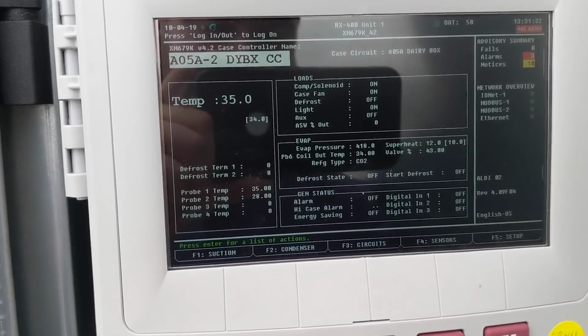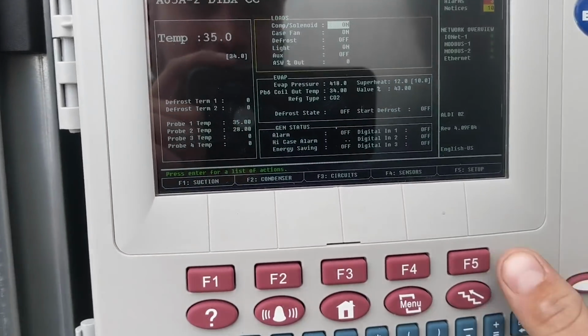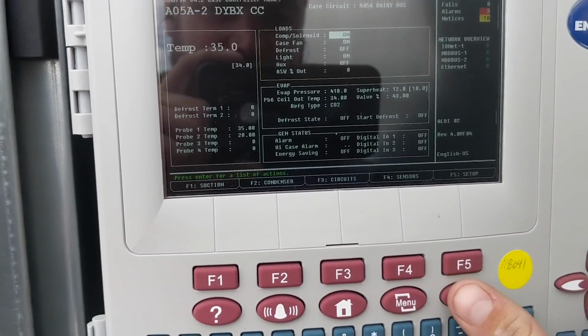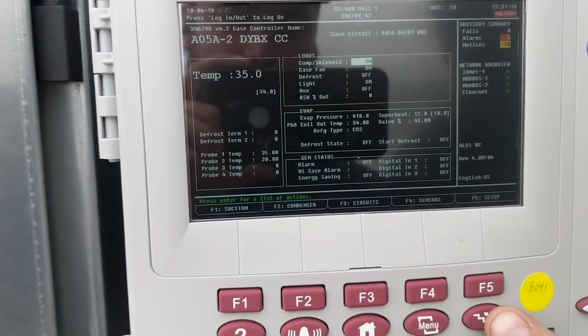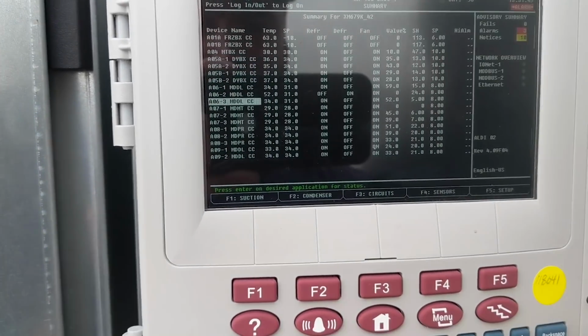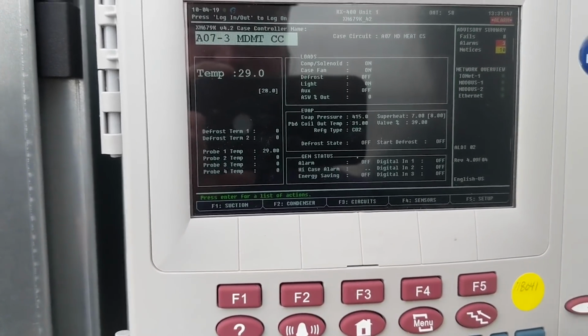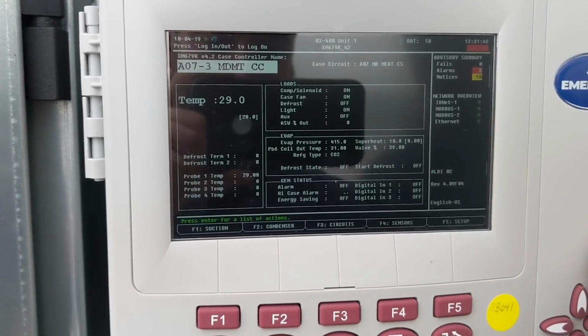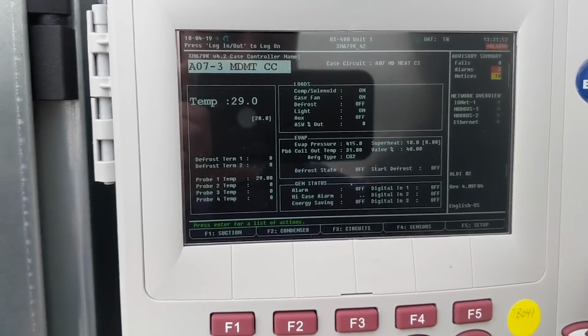So as long as the superheat isn't low, it's going to keep opening the valve till it hits its predetermined spot where I had limited the valve opening. We got our meat cases here. Each case has its own controller, own temp sensor, own valve. I'll show you downstairs a little bit.